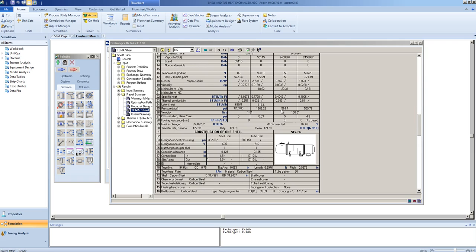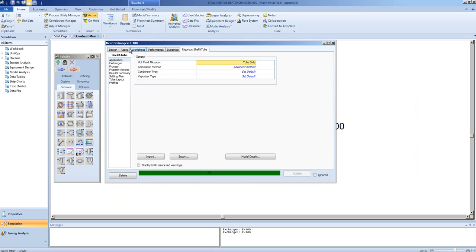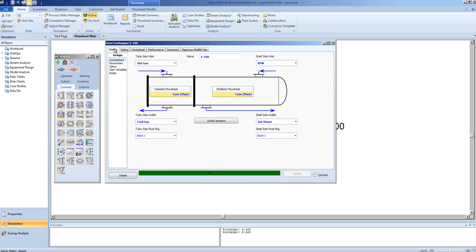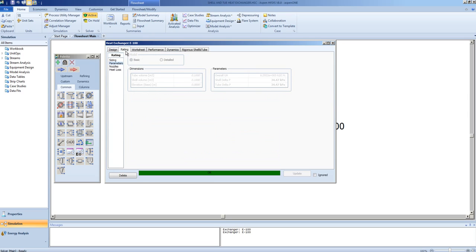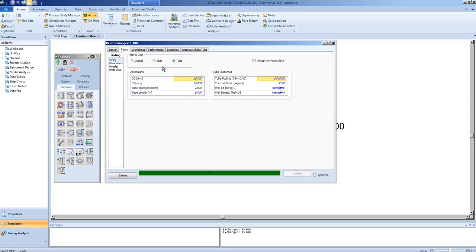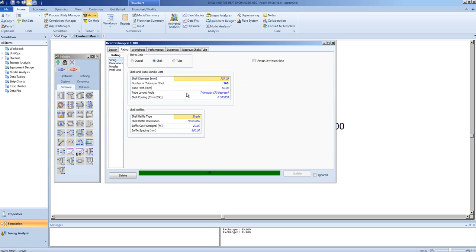We can even get a TEMA sheet for the exchanger. Note, if you have an exchanger in service already, it will have a design and a TEMA sheet. You can create that exchanger or a model of that exchanger in HYSYS by specifying the rigorous shell and tube model and then entering the information on the model under the rating tab. Under the sizing sheet, you can fill in the information for the tubes, the shell, and overall.